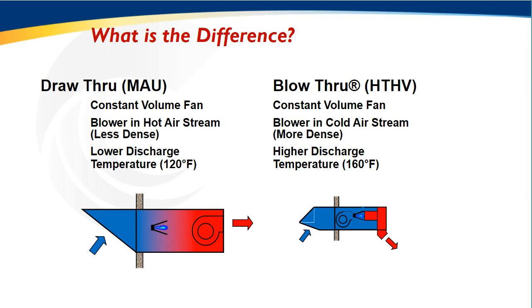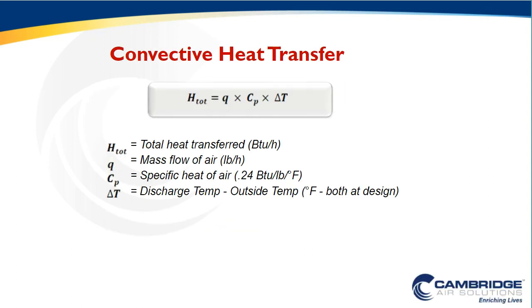However, in the HTHV system, since my blower and motors and bearings are in the cold air stream, I can dial my discharge temperature up to 160, and those motors are happy as a clam. Lower mass flow rate and higher mass flow rate. We don't often talk about mass flow rate when we are looking at designing HVAC systems, but mass flow rate is really the core concept to this whole equation, which is the equation for convective heat transfer, which many on the call I might challenge we haven't seen since our intro to thermo days back in university.